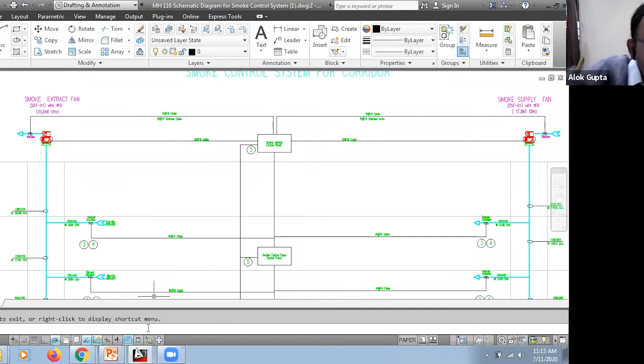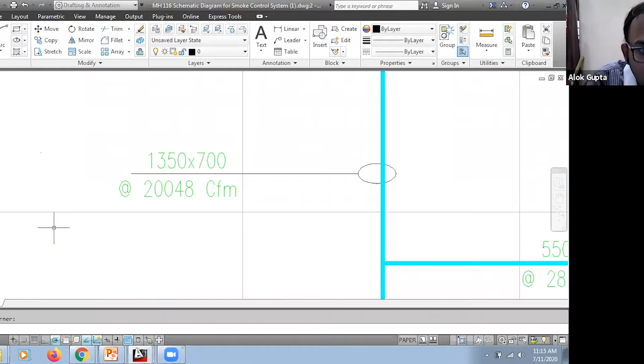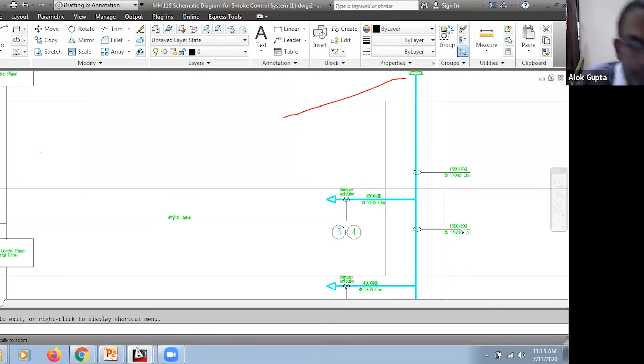So this is a very good design, what I can say. And on every floor we can see that we are exhausting more air, around 20,400, and we are supplying less air. So this is said to be a good design. I'll just show you. You see that we are supplying less air. So in case of exhaust, as per NBC, it is a very well designed system.